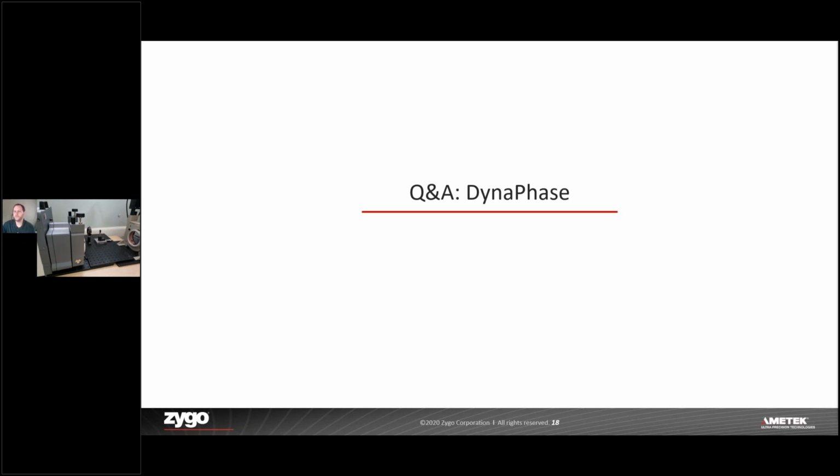Awesome. And next question, what vibration level do you need to switch from Q PSI to Dynaphase? Yeah, so that's actually a trickier question than it sounds to answer. Vibration actually has both amplitude and frequency components, both of which combine to really affect how vibration is changing your measurement. So because of that, there's really no hard cutoff on when you make the switch from Q PSI to Dynaphase.